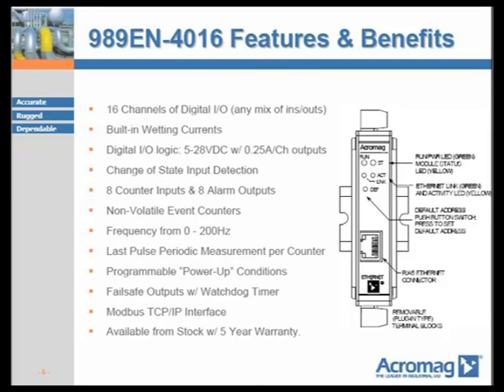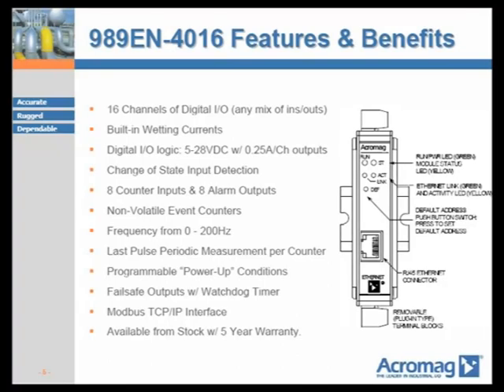Eight 32-bit configurable up-down counters and alarms are available. The counters will totalize and store data to non-volatile backup memory, so if power is lost and returns, the important count values will remain — no batteries are used or ever needed. Counters can handle frequencies up to 200 Hz without missing any pulses. Applications involving totalization from mechanical relays typically only need frequency inputs of 10 Hz or less in most cases.